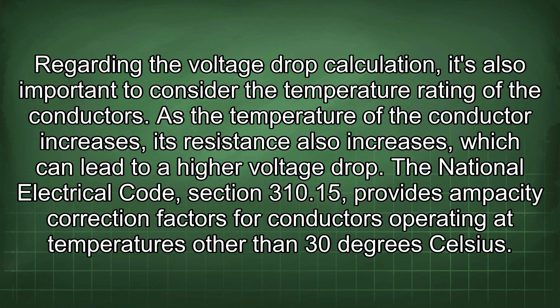Regarding the voltage drop calculation, it's also important to consider the temperature rating of the conductors. As the temperature of the conductor increases, its resistance also increases, which can lead to a higher voltage drop. The National Electrical Code, Section 310.15, provides ampacity correction factors for conductors operating at temperatures other than 30 degrees Celsius.